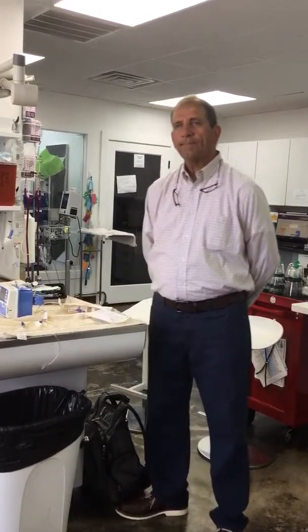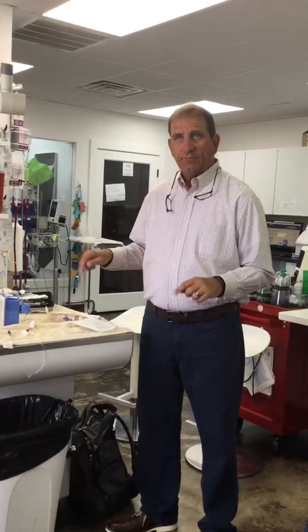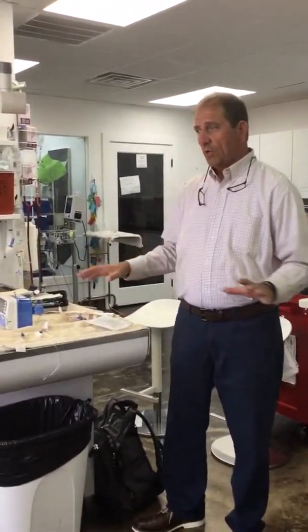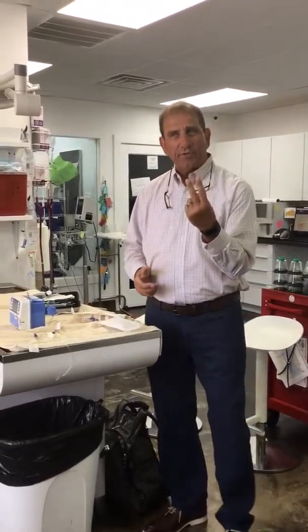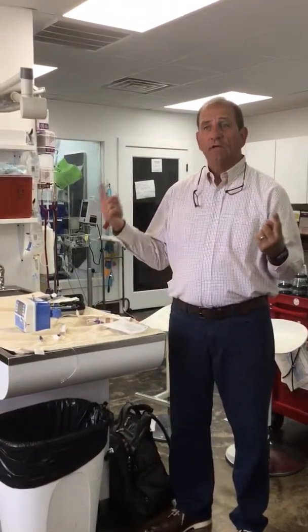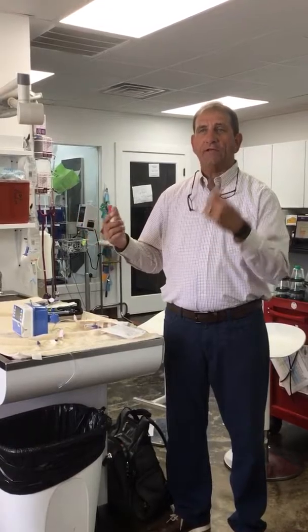So one question is, with Hospira and previously Baxter's, they would be calibrated to a specific line, Aspira, or depending on which line you purchase. Correct. Are these calibrated to a specific line? These have the ability that you calibrate it right here. I just calibrated these pumps to your tubing. Okay. So these are already calibrated. There's only 2 calibrations on the market: Baxter, Hospira. Hospira's 15 drop, Baxter's 10 drop.